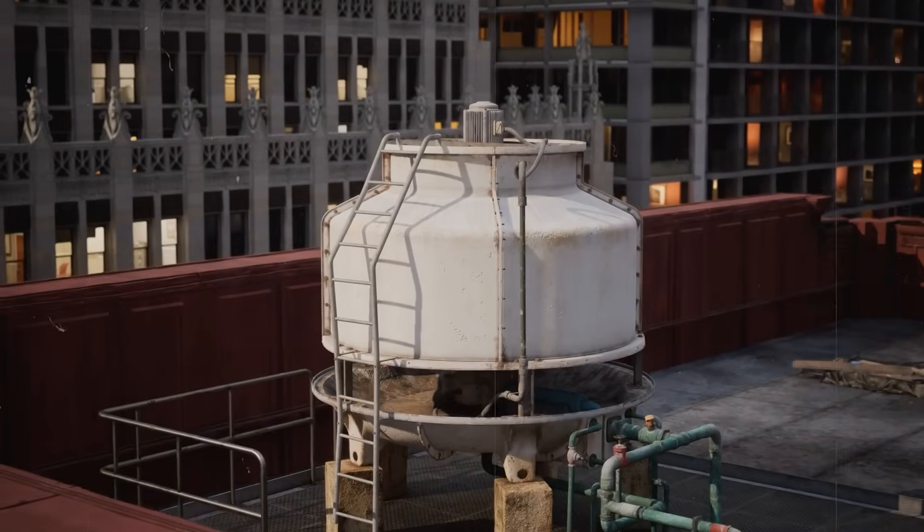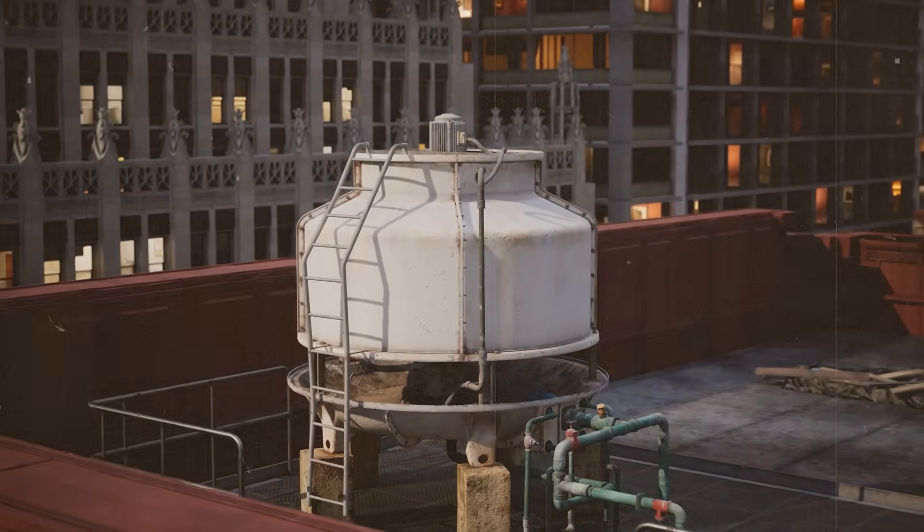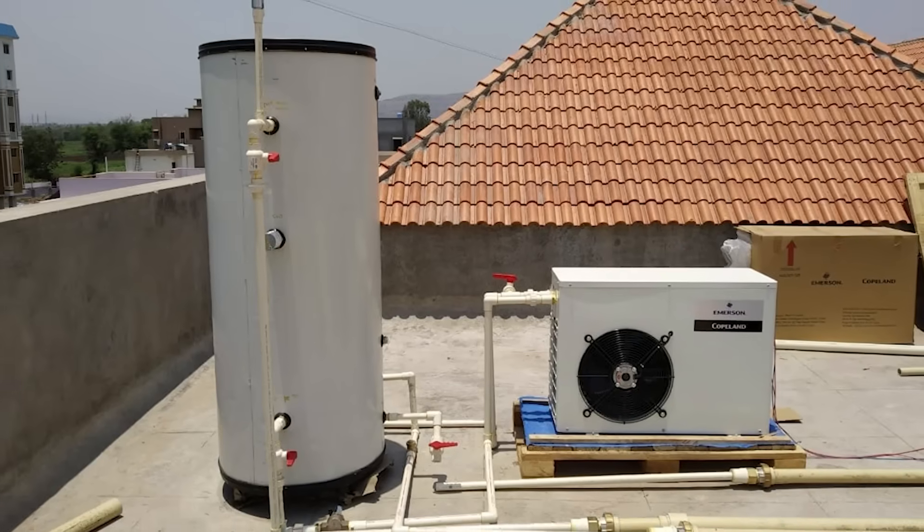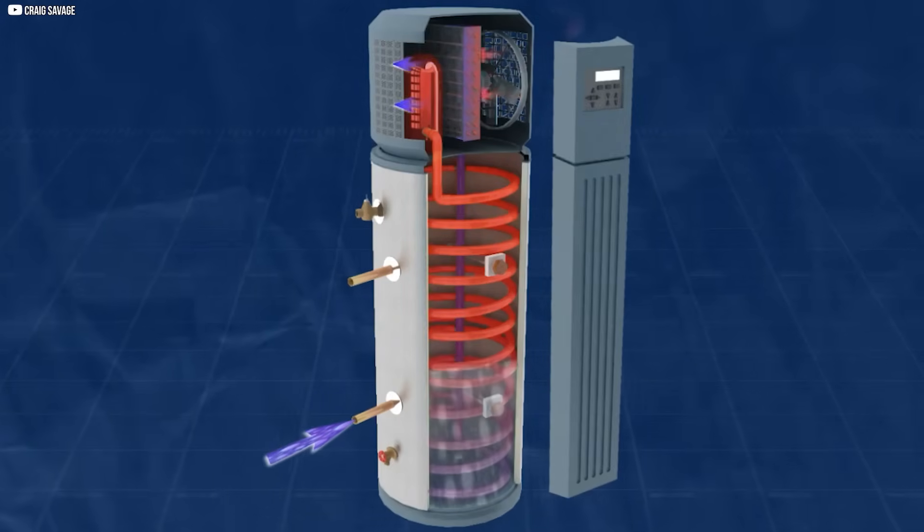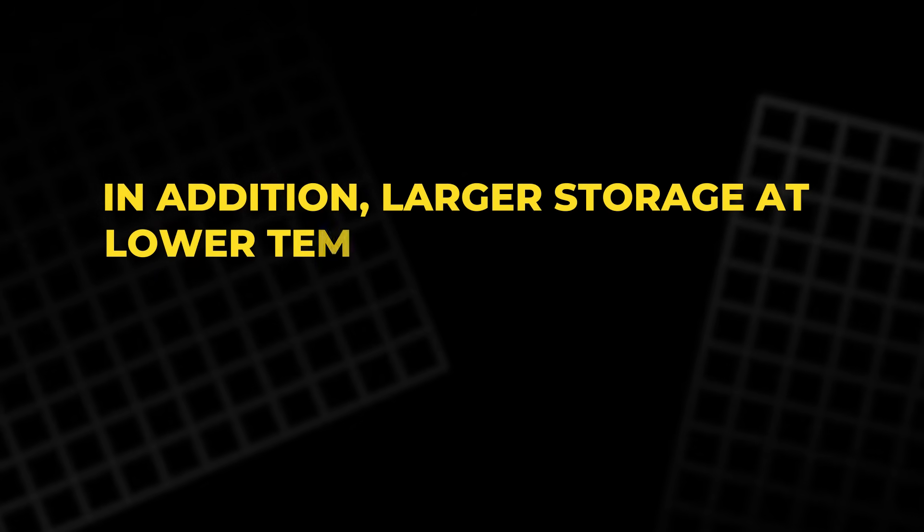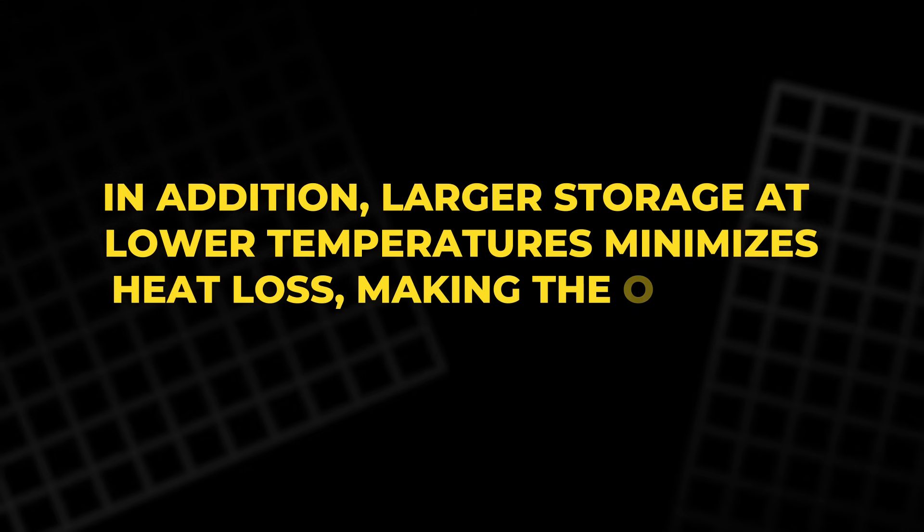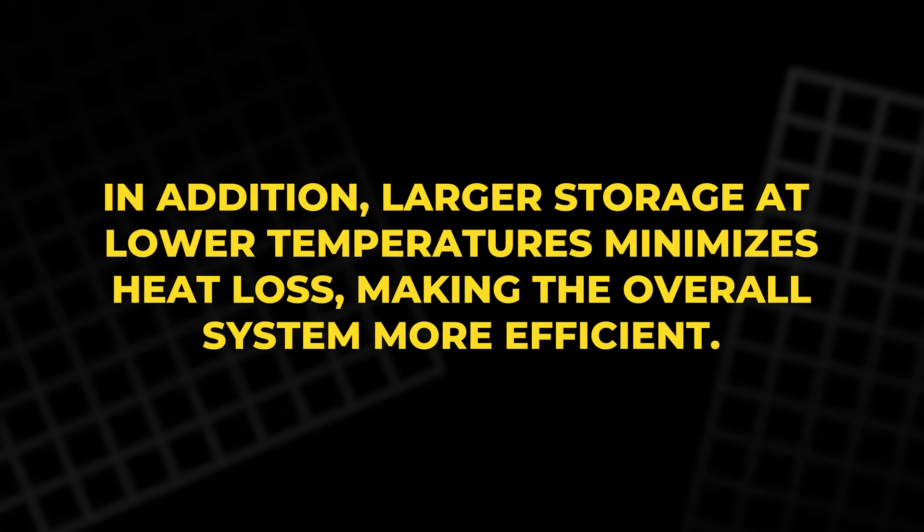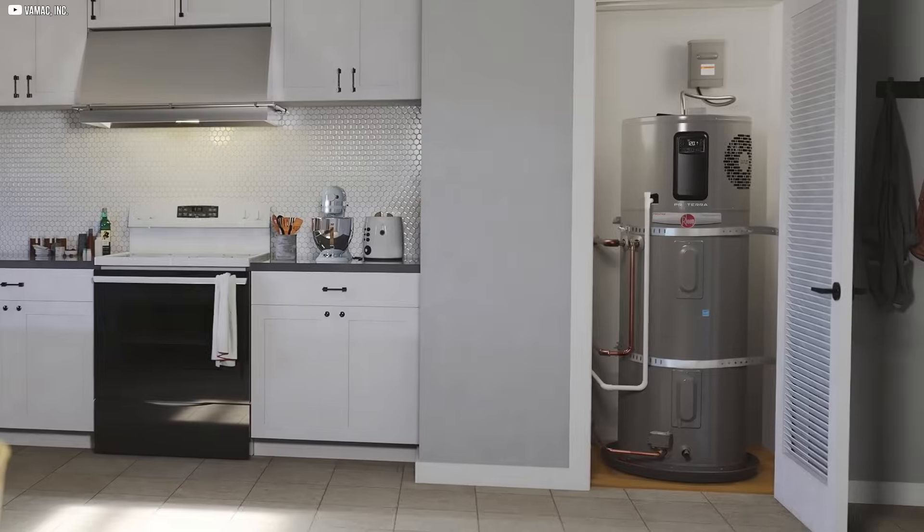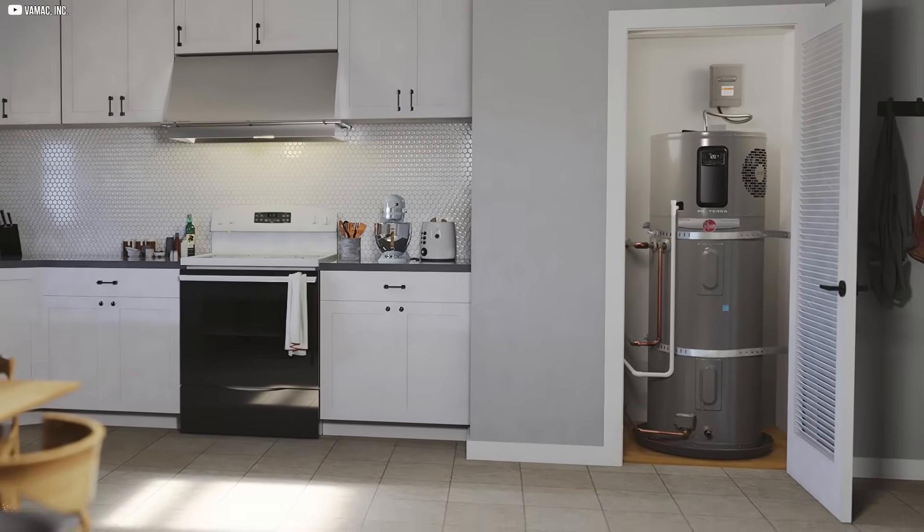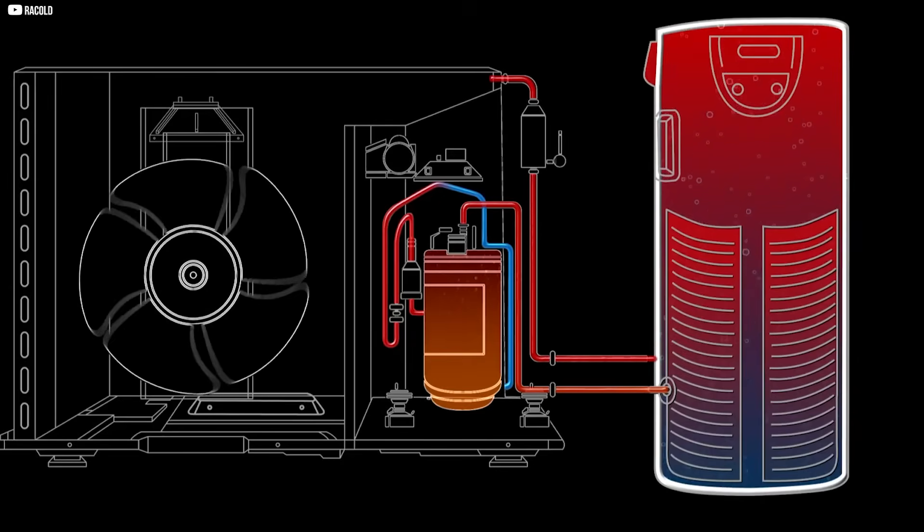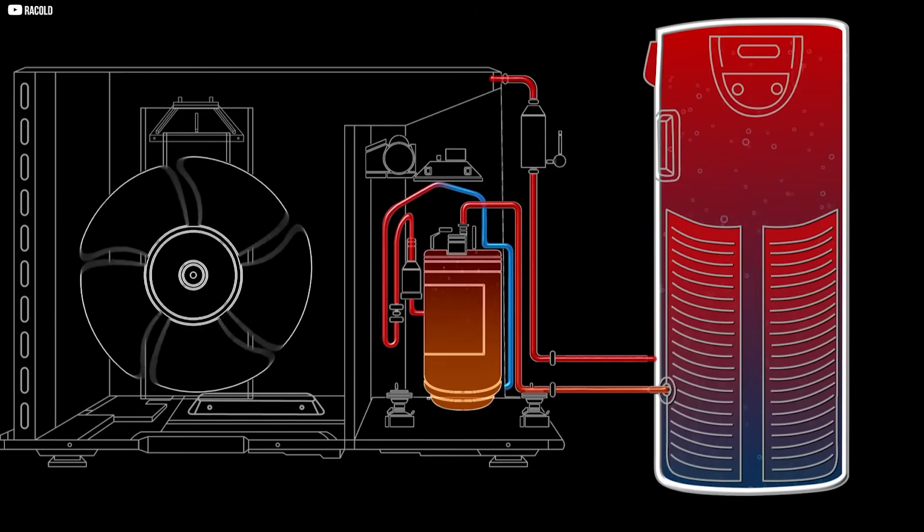By using a larger tank, you can store enough hot water for daily use at a lower, more energy-efficient temperature. This avoids the need for constant reheating, which can drain energy. In addition, larger storage at lower temperatures minimizes heat loss, making the overall system more efficient. This approach contrasts with smaller tanks that must maintain higher temperatures to ensure hot water availability, which increases energy consumption.